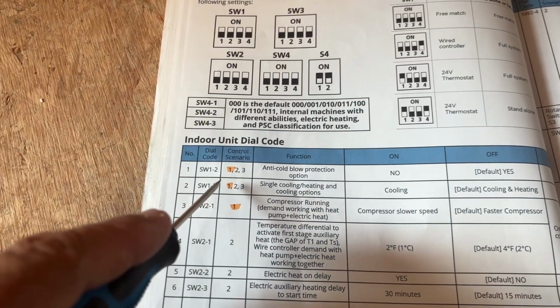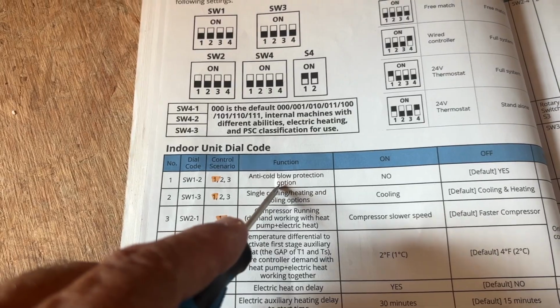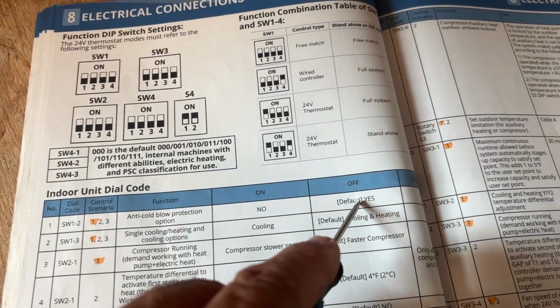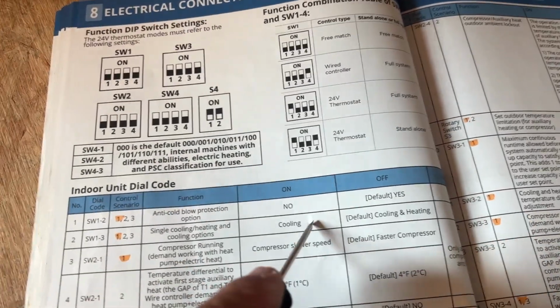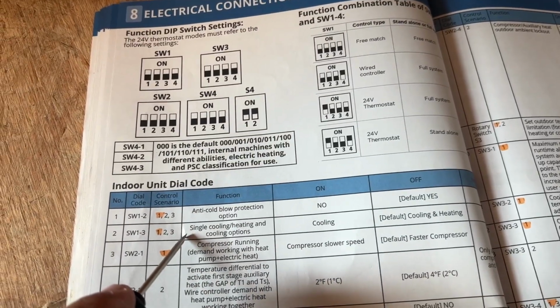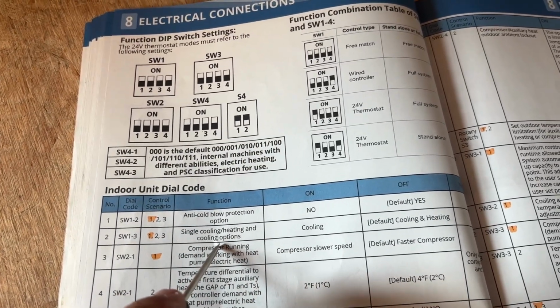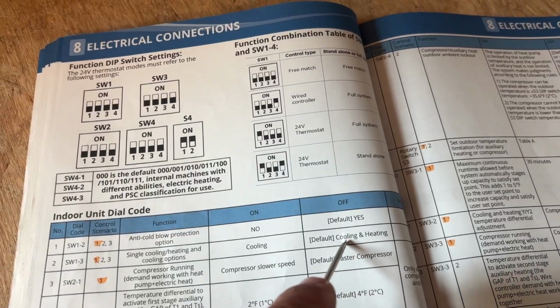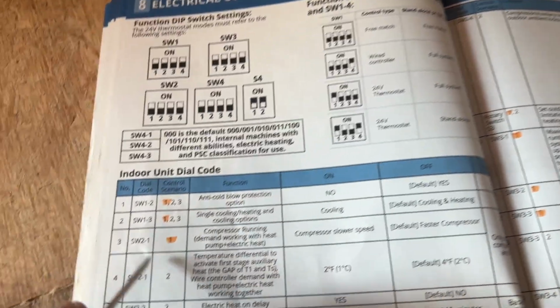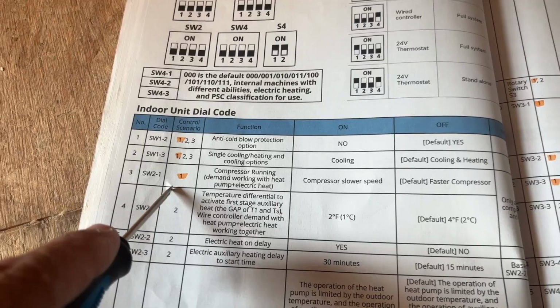All right, SW1-1 we have set according to our specific model for a 24 volt system. The second switch on that is the cold blow protection. We're going to keep that on. It's defaulted on to yes in the off position. The single cooling or heating and cooling control, since this unit is doing both cooling and heating, we're going to leave the default alone on that.